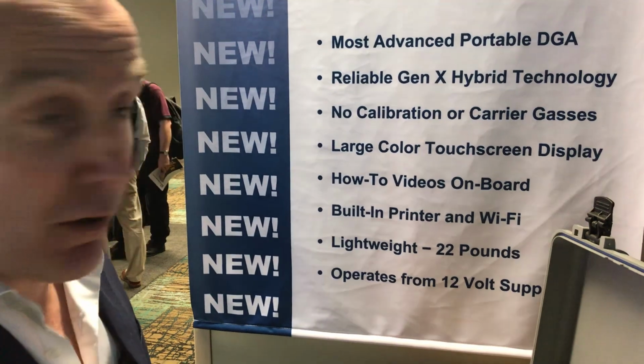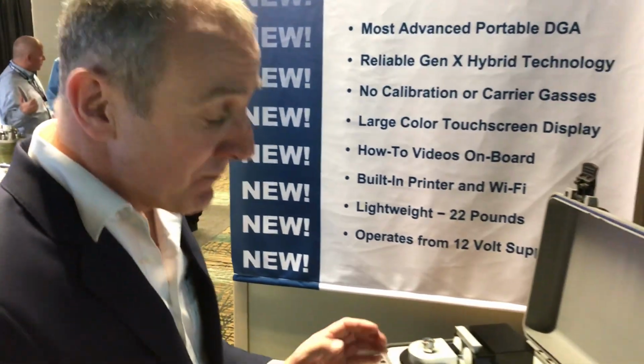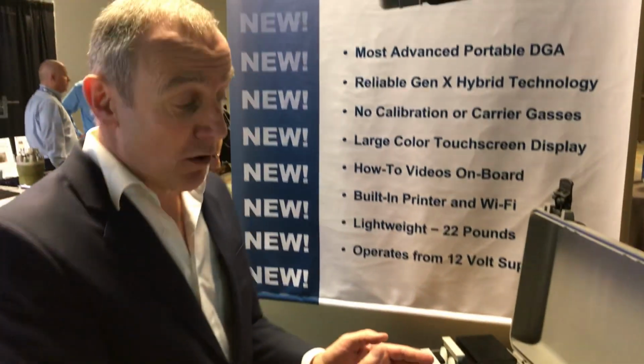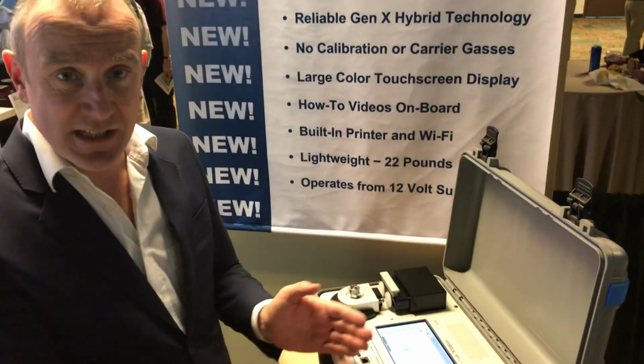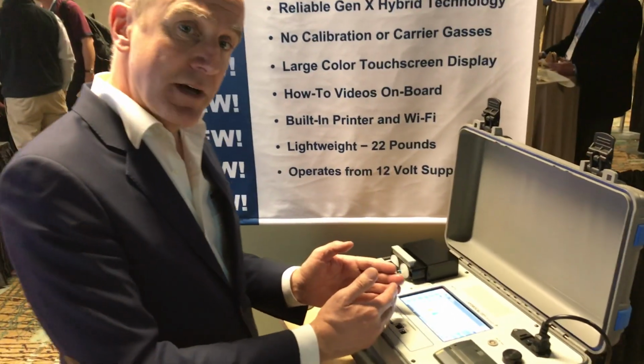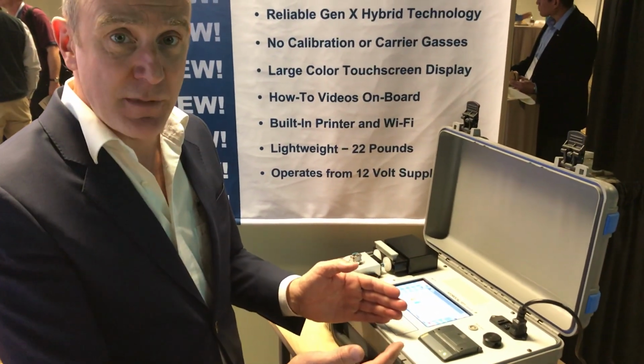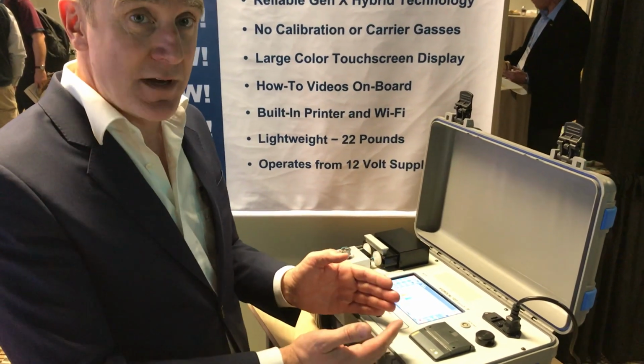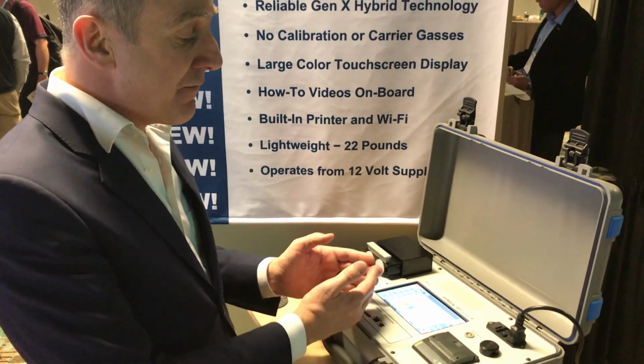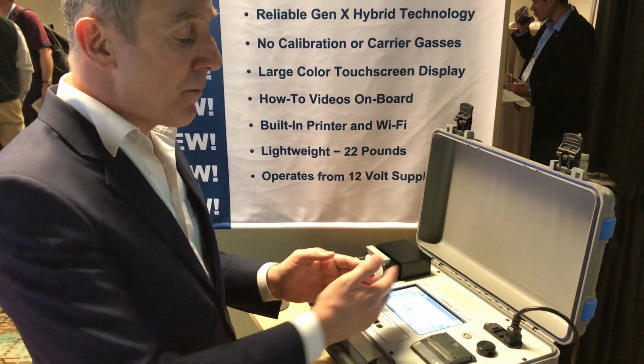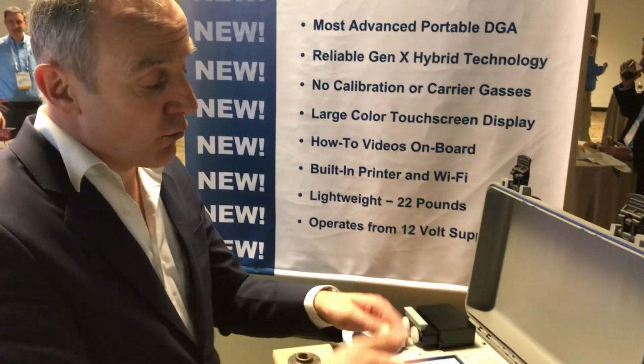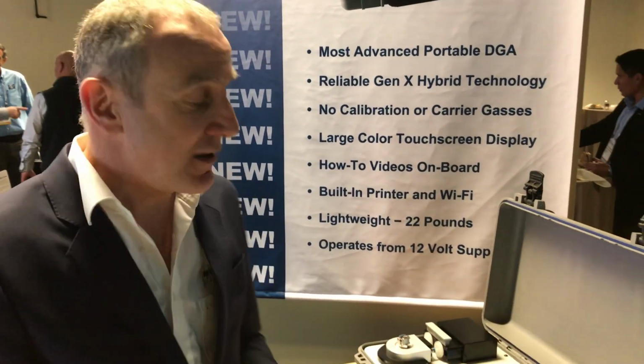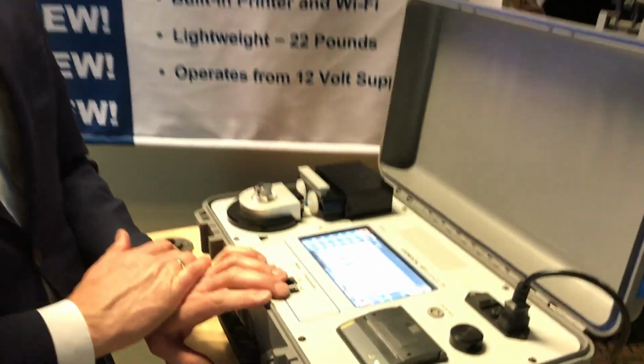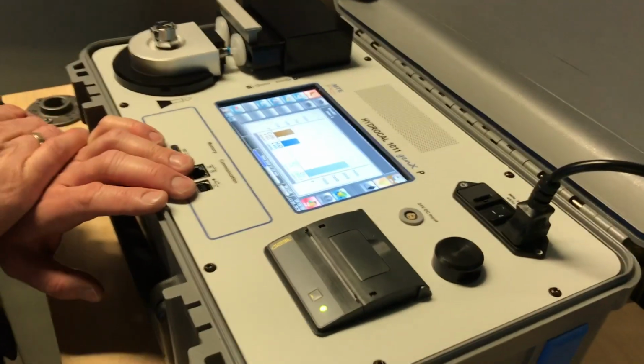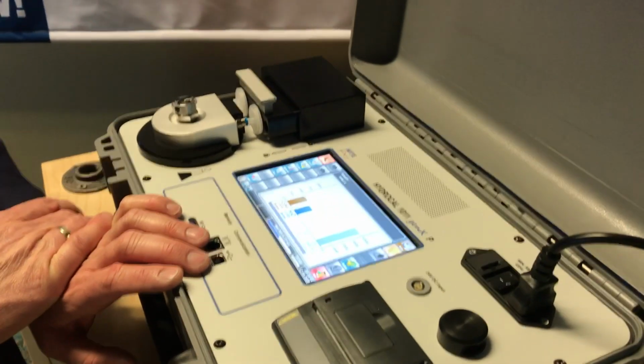and big advantage, can be operated from a 12-volt power supply from a car battery. This can be an advantage because the operation cycle to obtain one measurement is approximately 55 minutes, which includes a 20-minute warm-up time. So if the device is already warmed up on the way to the substation or when entering the substation before getting ready by the car battery, this eliminates important time.